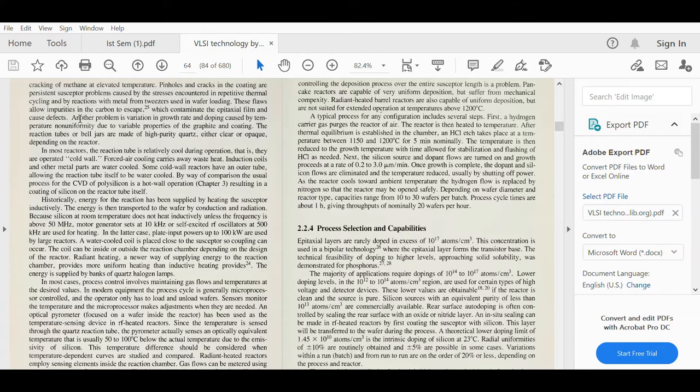Another problem is variation in growth rate and doping caused by temperature non-uniformity due to variable properties of the graphite and coating. The reaction tubes or bell jars are made of high purity quartz, either clear or opaque, depending on the reactor.